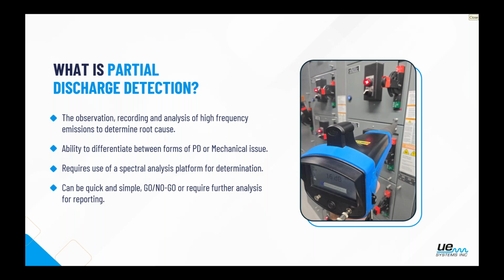To the point we can also see if we have multiple events happening at the same time, such as a loose component that does have an arc happening within that cabinet, which would be a much more severe issue and require a different approach. Now, it typically does require the use of spectral analysis, further analyzation to determine these sounds and frequencies.